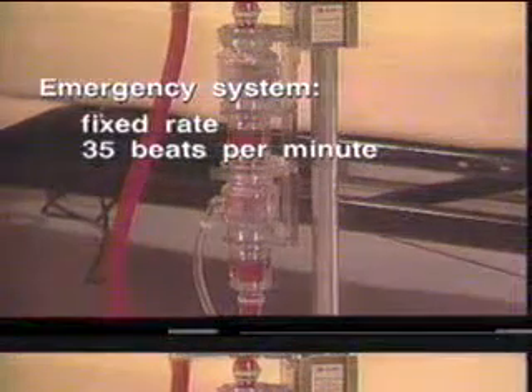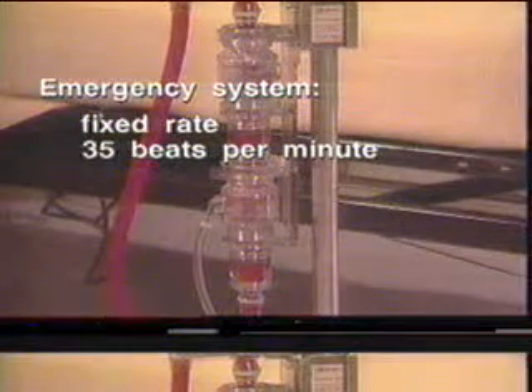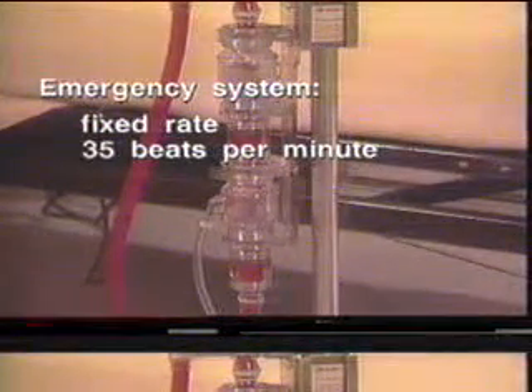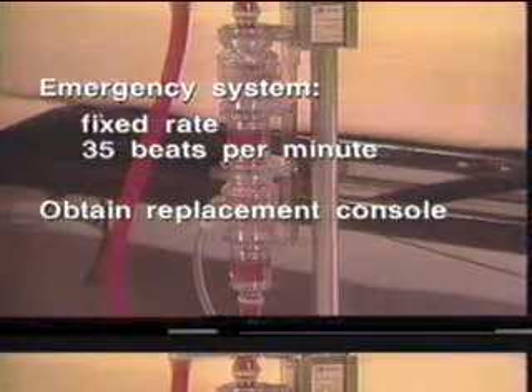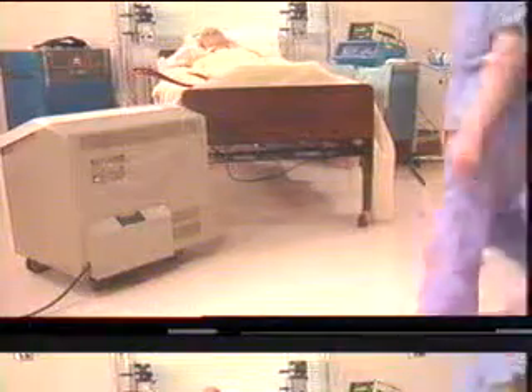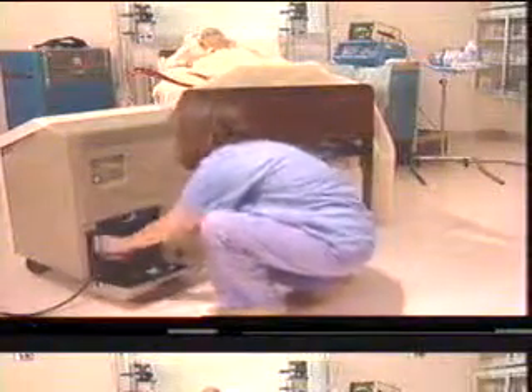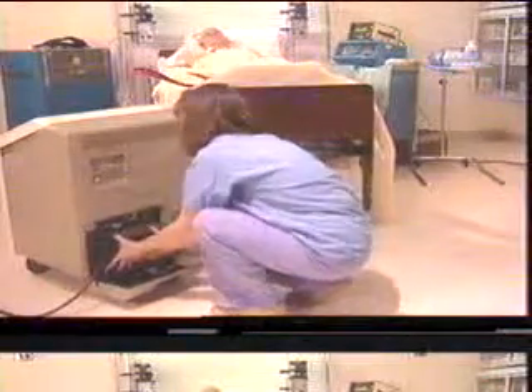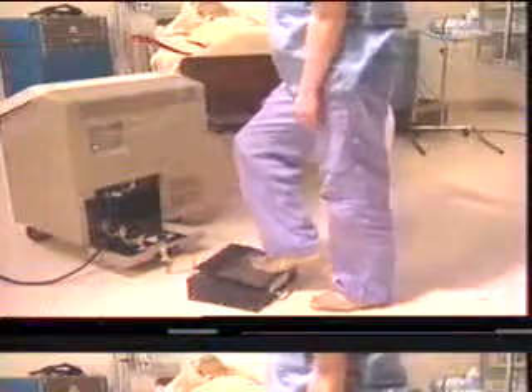The emergency system on alarm sounds if the console microprocessor malfunctions and is unable to determine flow and adjust rate accordingly. In this condition, the console reverts to a fixed beat rate of 35 beats per minute, regardless of atrial drainage. Should the system activate, the patient will continue to be supported, but arrangements should be made to switch to another console. In the event of a total loss of console function, a foot pump is located in the rear compartment of the console. Foot pump is accessed by moving the foot pump handle to the horizontal position and depressing the foot pedal. The pump can be used to manually operate 1 or 2 blood pumps until a replacement console can be obtained.